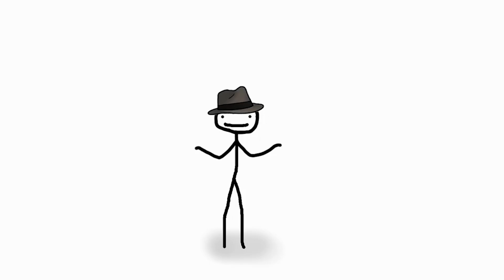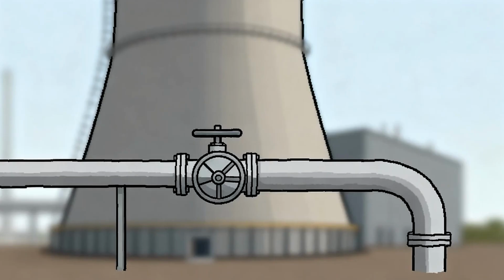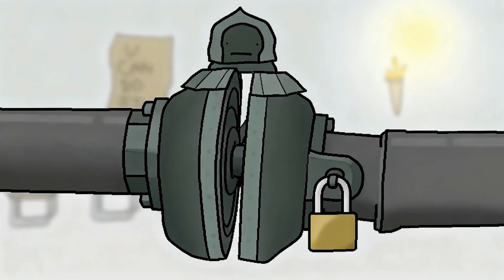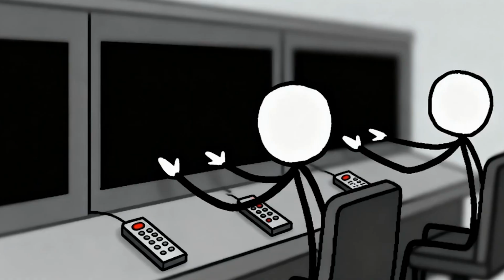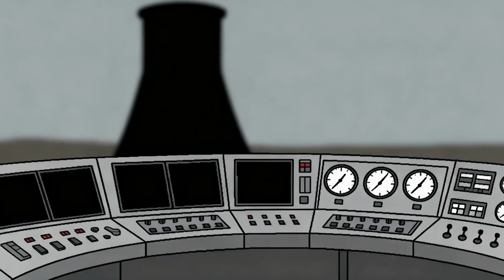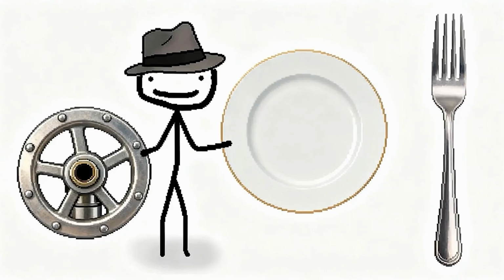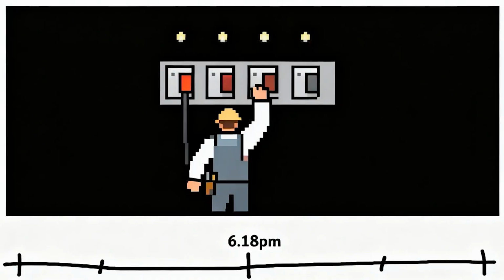And here's where the valve becomes the villain. The isolation condenser valves in Unit 1 were fail-closed by design. When DC power vanished, they locked shut. Operators had no remote way to reopen them. The reactor was blind, instrumentation dark, and the one backup system that didn't need pumps was now sealed off by a piece of metal the size of a dinner plate.